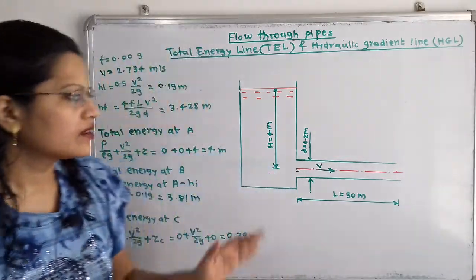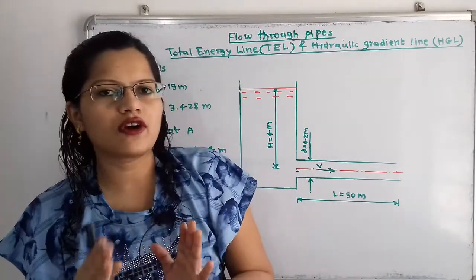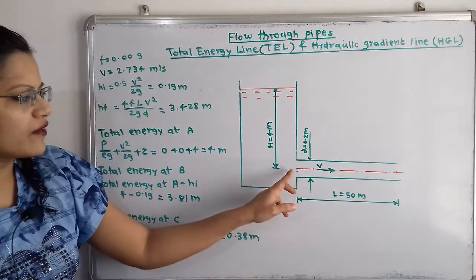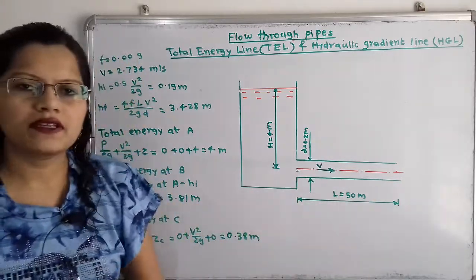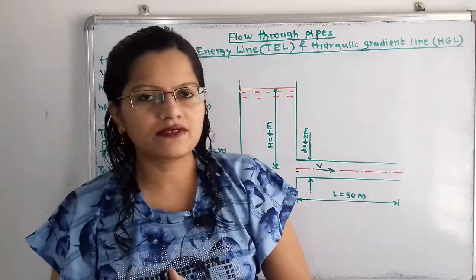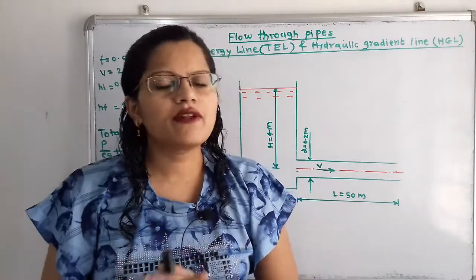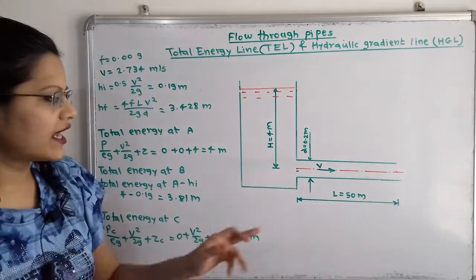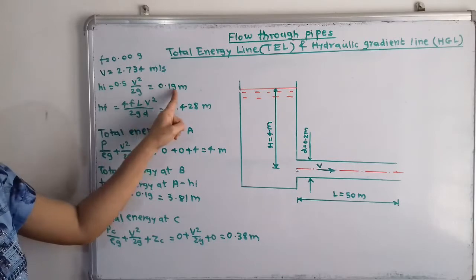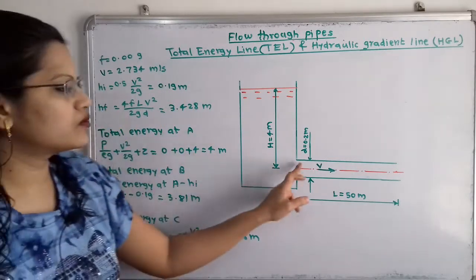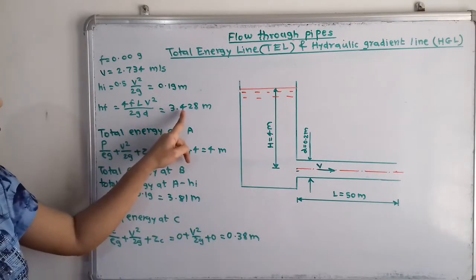Water from the tank enters the pipe, causing a head loss at the entrance. As water flows through the pipe over a length of 50 meters, it is in contact with the pipe surface, causing friction losses. The head loss at the entrance HI = 0.5 V²/2g = 0.19 meters. The head loss due to friction HF = 4FLV²/2gd = 3.428 meters.